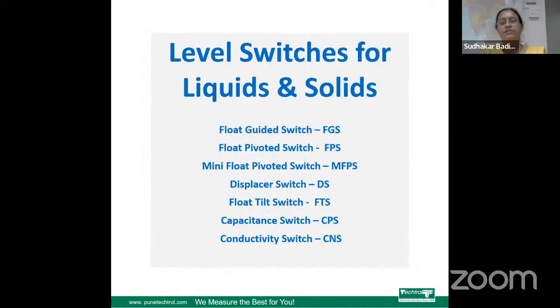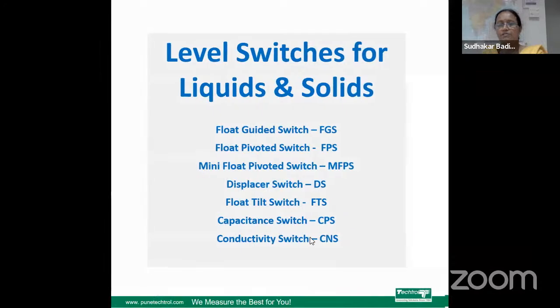Now let us see level switches for liquids and solids. Here we are going to see float type level switches, that is float guided switch, float pivoted switch, then miniature type float switches, then displacer switches, float tilt switches, capacitance switch, and conductivity switch.